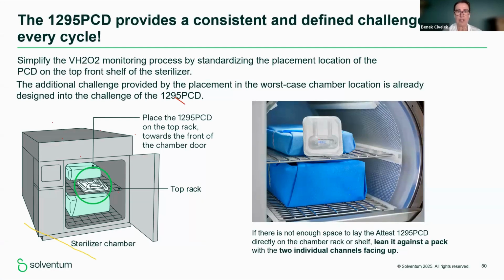We received the questions about where to place the biological indicators inside a chamber. Usually, we expect the sterilizer companies or the manufacturers to tell about the most challenging situation inside the sterilizer, or the worst case scenario, the worst point, let's say. Here, in fact, this design is providing the user the worst case scenario because the design itself has a challenge. But in general, when placement is asked, we can say that you have to place this PCD on the top rack towards the chamber door, which is tested to be the worst condition area. If you don't have any place to put this as in the left picture, then you can lean it against a pack, but always these two channels should be up.